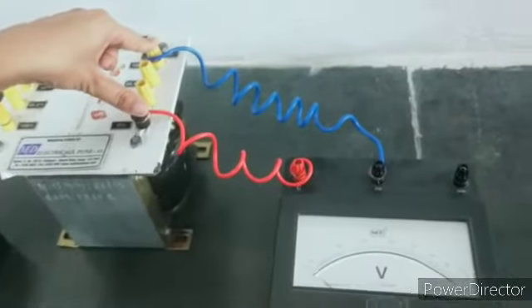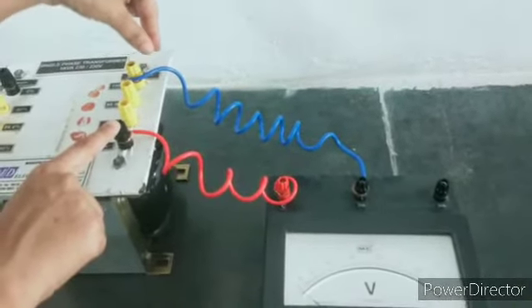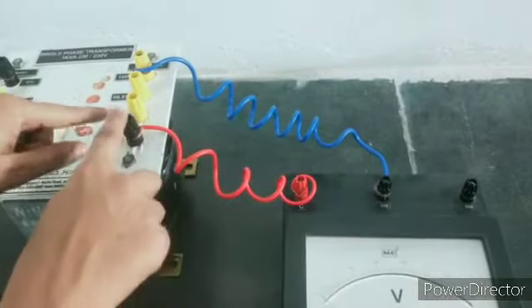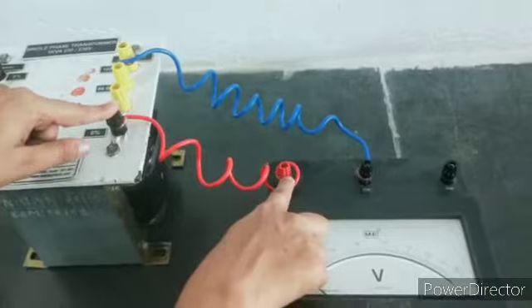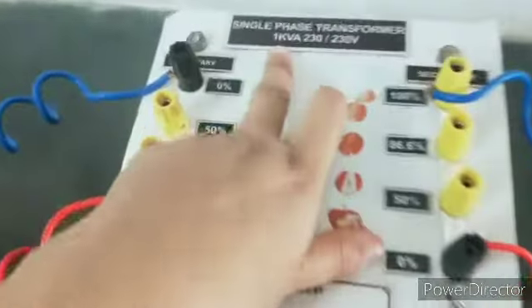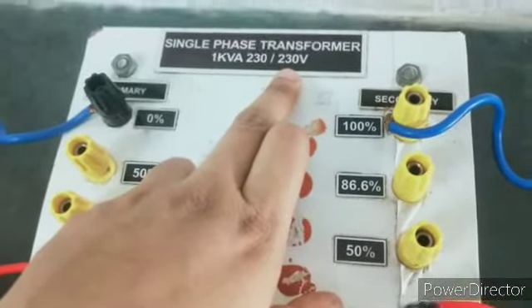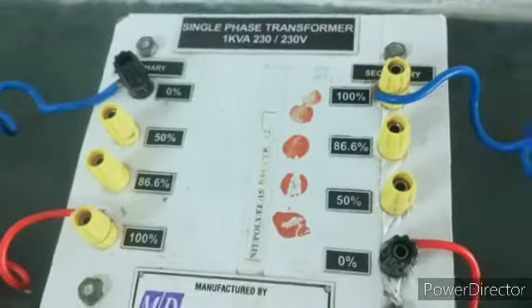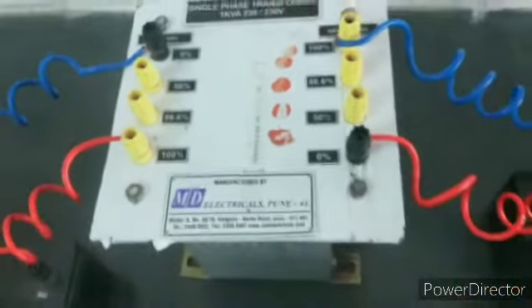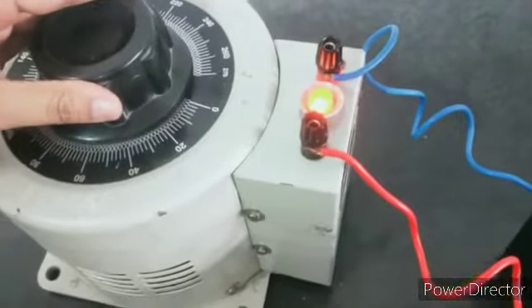As we mentioned in the circuit diagram, the voltmeter has to be connected in parallel on the secondary side of the transformer. So the starting point of the secondary winding is given to the range, and the ending point is connected to the common. The function of isolation transformer — it is a one-to-one transformer. Here we have a single phase transformer 1 kVA, with primary winding 230 volt and secondary winding also 230 volt, so it works as an isolation transformer — meaning whatever voltage we give on the primary side, the same voltage should be obtained on the secondary side. Now we will turn on the AC supply, and our auto transformer is at 0 — now we will vary it.